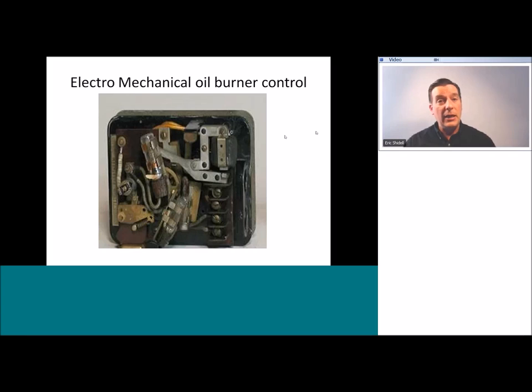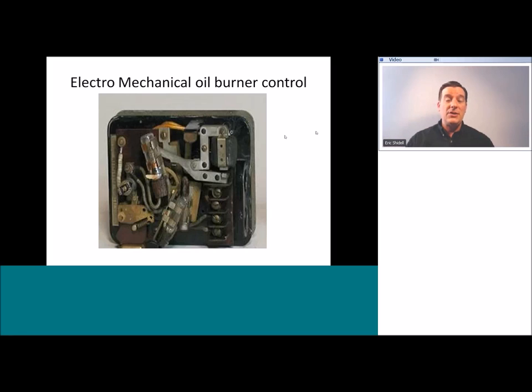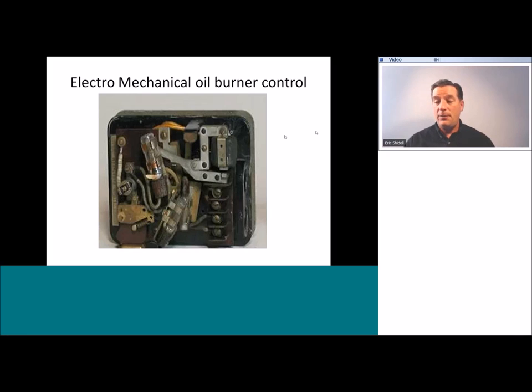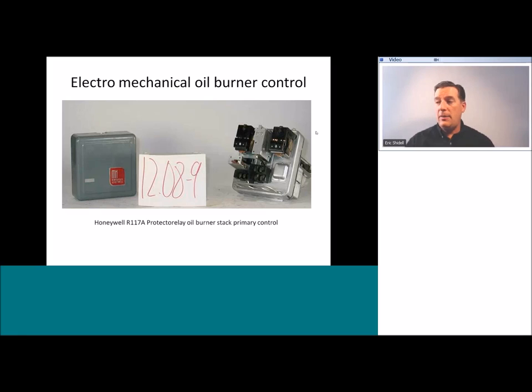This was the highlight of electromechanical controls — about as sophisticated as they got in our industry. It allowed for automatic ignition of fuel oil and safety shutdown if the fuel oil did not light, bringing a much greater level of safety. But it had its limitations: it would normally have to allow fuel oil to flow to the burner nozzle for a significant period of time before shutting things down. So it would minimize an unsafe condition but couldn't prevent it entirely. This design was with us for literally decades — the device pictured is from the 1940s, and a similar unit was still standard into the 1980s.